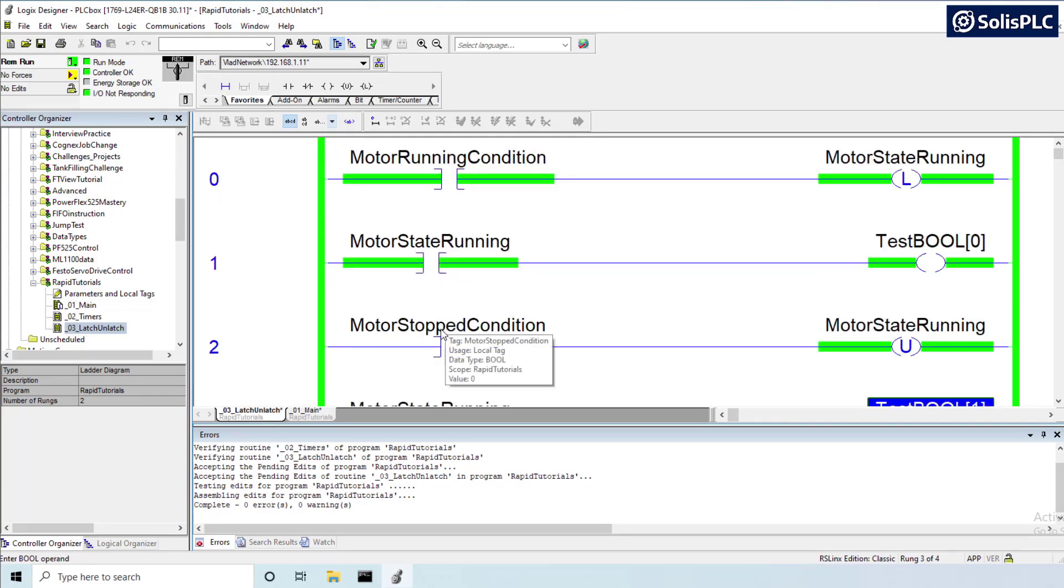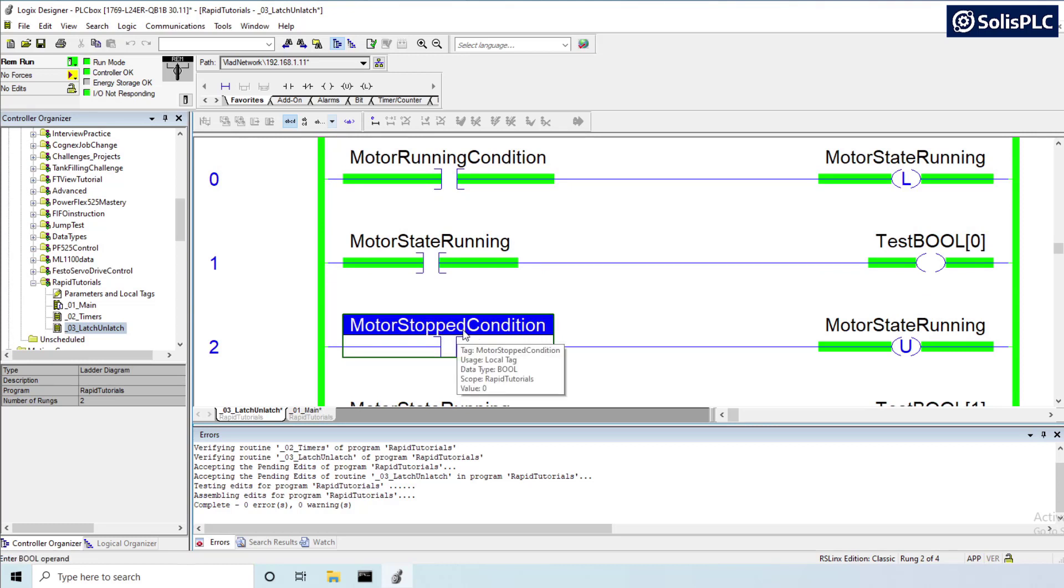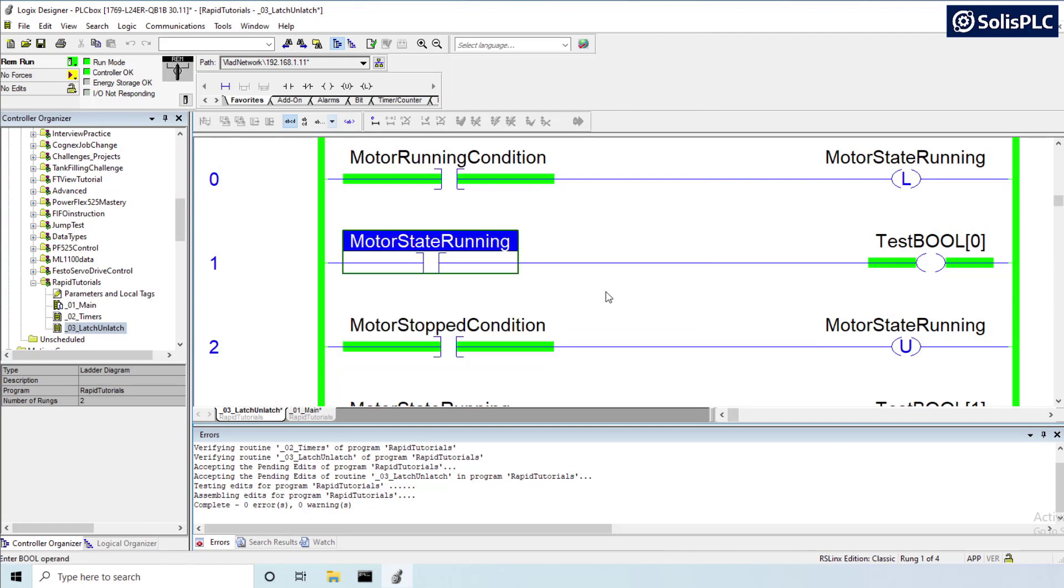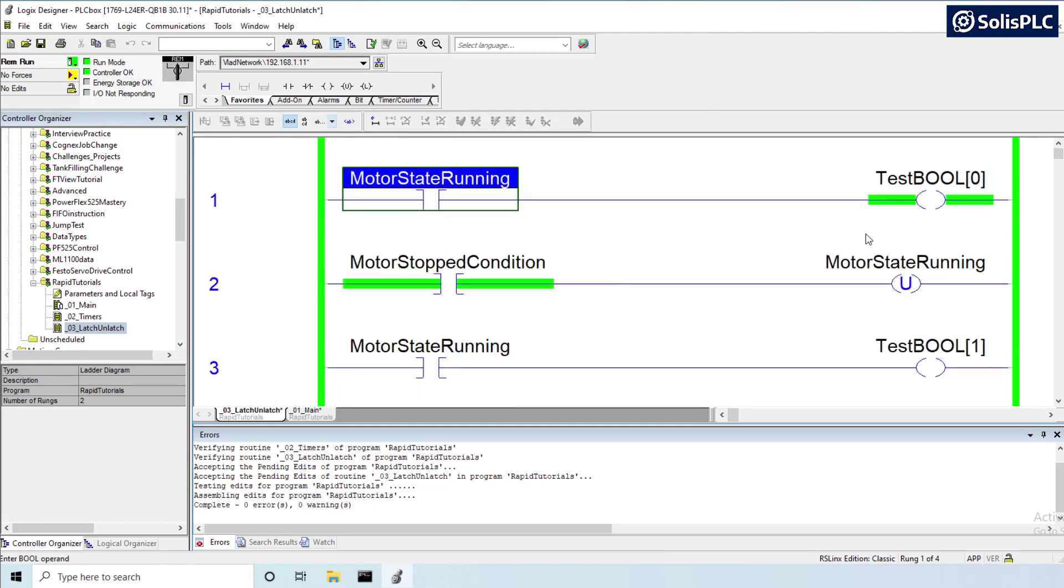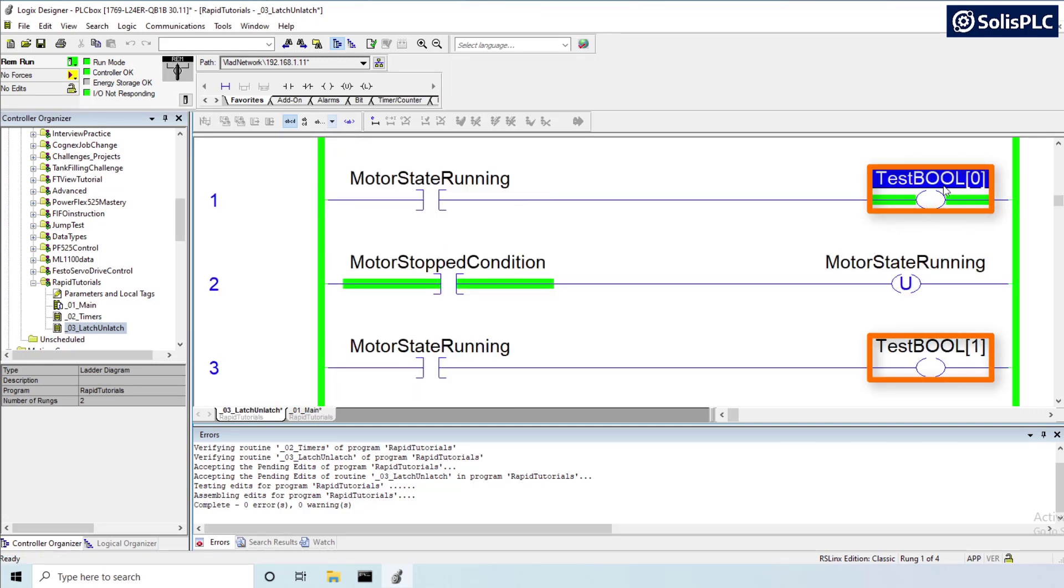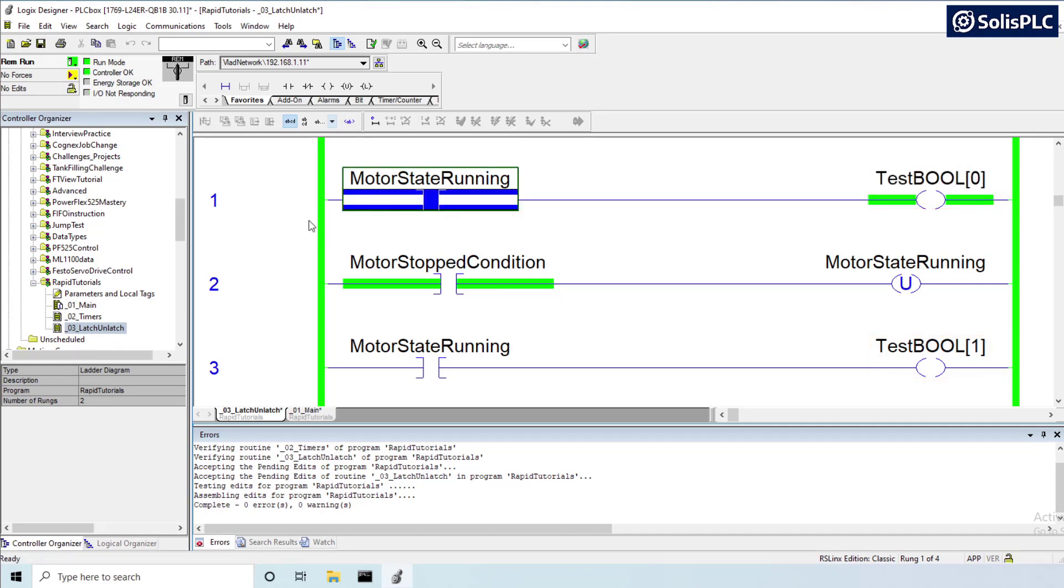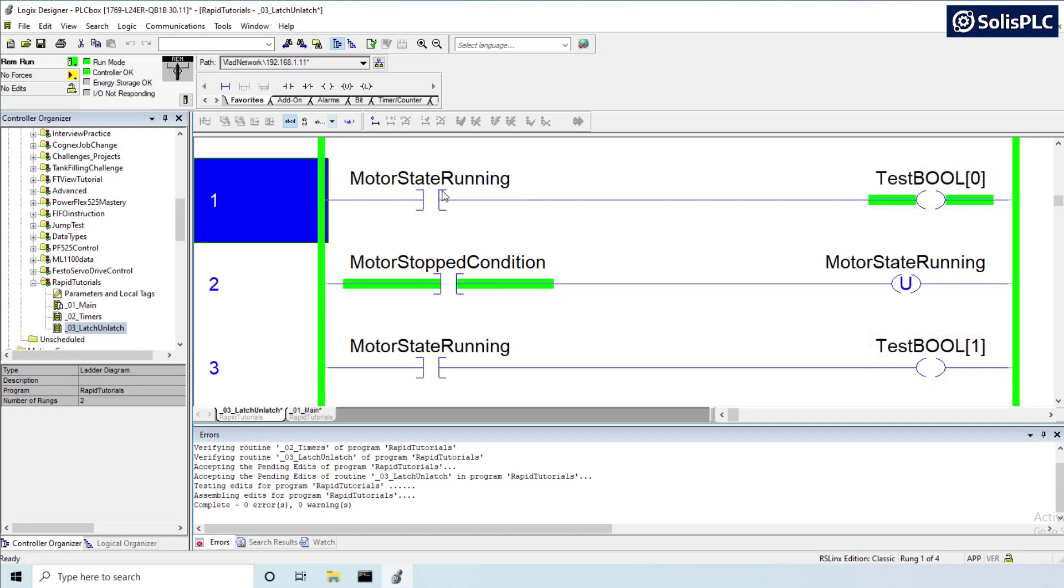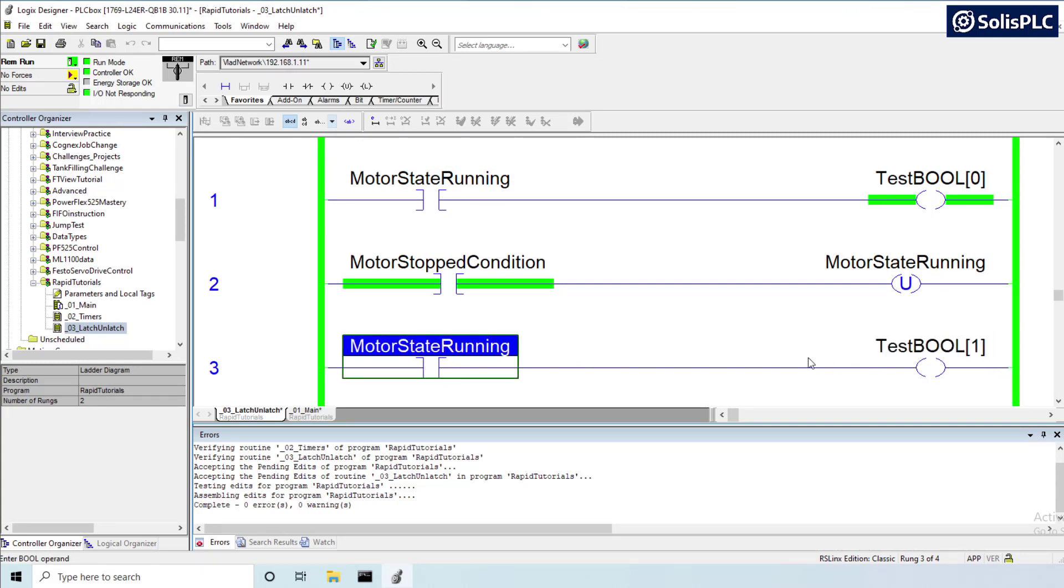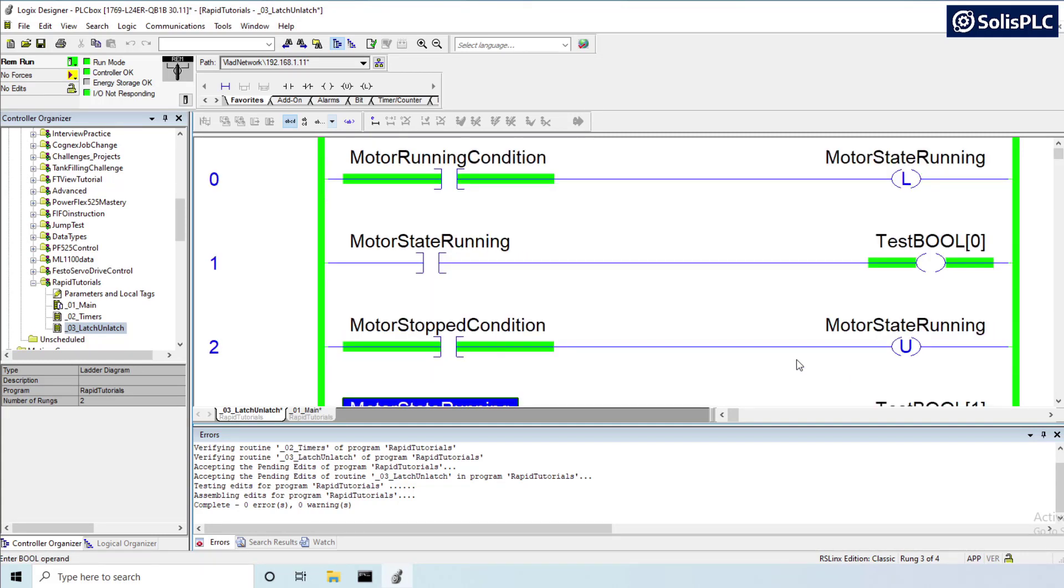Now the problem arises if the stop condition is also true. So I'm going to right click this and I'm going to toggle this as well and what you'll notice is that in rung one my test boolean zero is still energized despite me seeing that motor state running is de-energized and here at the very end it is de-energized. Now why is this happening?